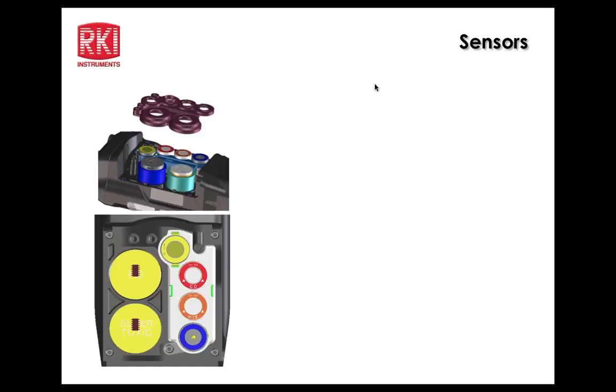Sensors. Here's a graphic of the cover removed from the back of the unit, so you can see a rubberized gasket assembly at the top, if you want to call it that, and then there are the sensors below that in the unit. So you have on the right-hand side the LEL sensor, the CO sensor, H2S, and O2, which have orientations very much like the 2012 and 2009 do for mounting them in their wells. And then the smart sensors will go in the left-hand side, obviously. The PID will go in the top section, or closest to the LEL sensor, and then the super toxic sensors or infrared sensors can go in the bottom one.